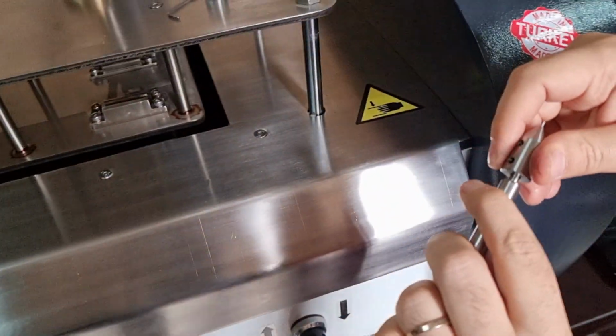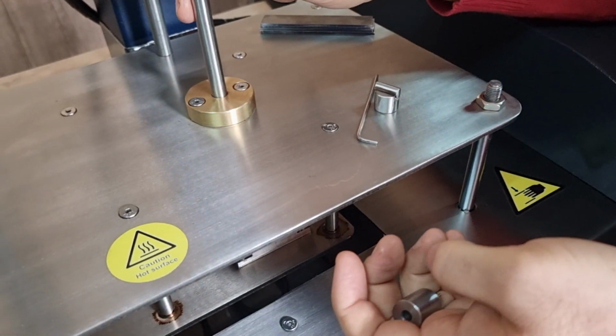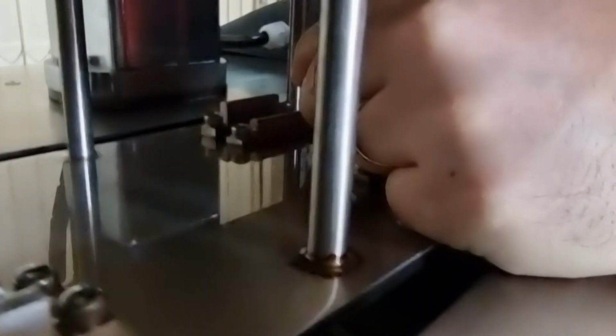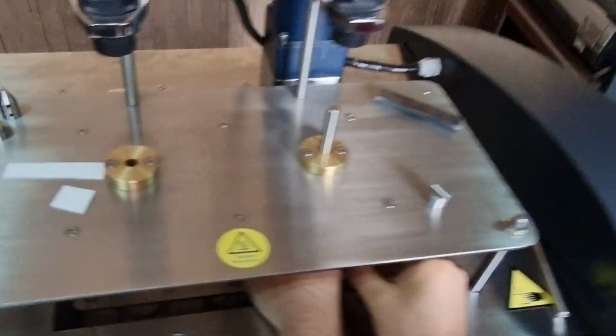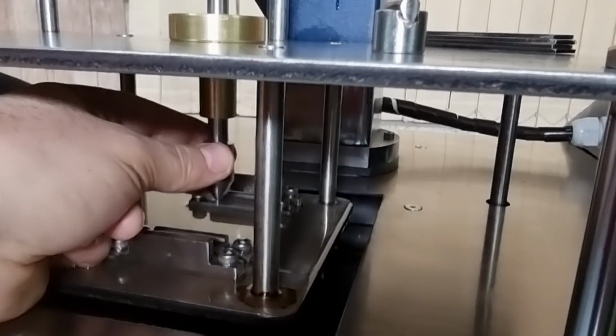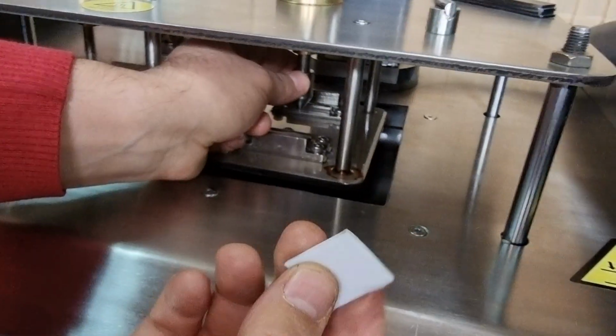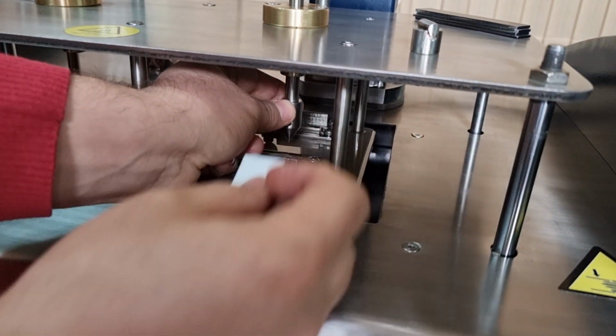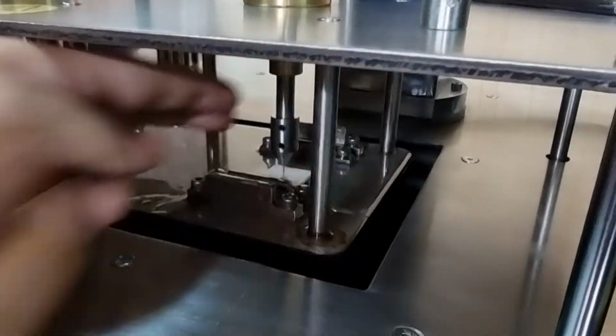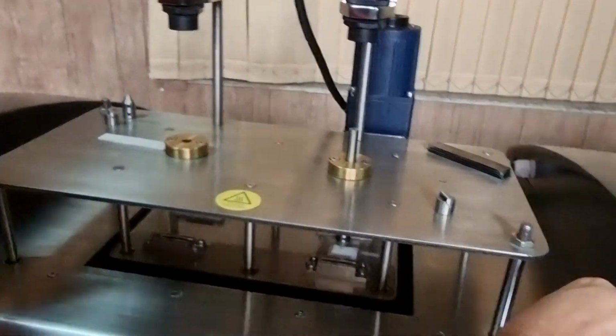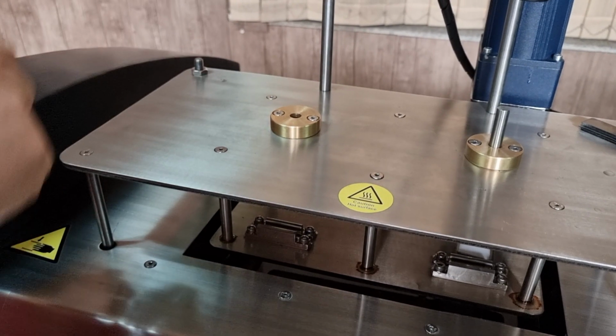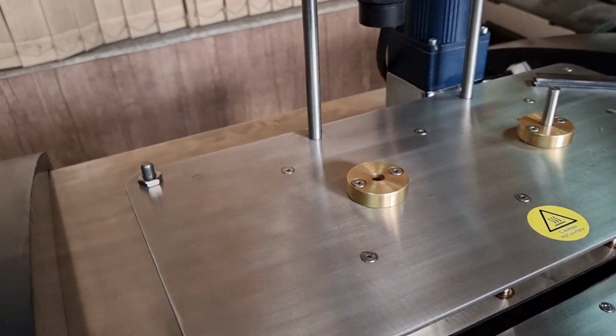First of all, for example, for Vicat testing, you will need this Vicat head here. You will put the rod here, and from the bottom side you need to assemble it here on the rod. Then tighten this set screw. Yes, like this. And the sample of the Vicat testing, the dimension and thickness is defined in the standard. You will put it in the middle section like this. For the second sample, if you have a sample, you can put the second sample. I just have one sample here.